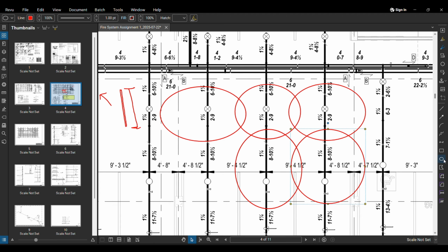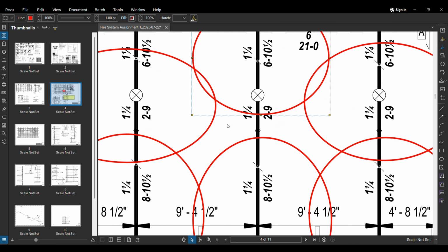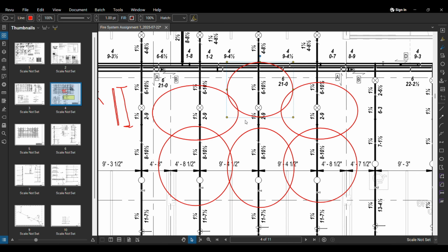So I'll just make another one here like this, right? If I move this particular sprinkler, let us say 3 feet this way, in the upwards direction, the north direction, can you see this particular area is now devoid of any water that comes from the fire sprinkler systems. And then if I move this sprinkler system here, let us say 2 by 2 feet here as well, can you see this area is now not being covered by the sprinkler systems at all.